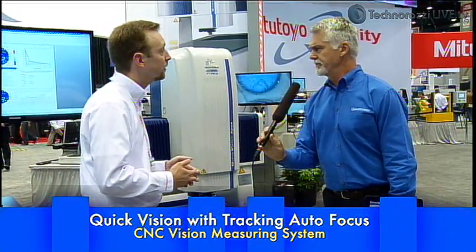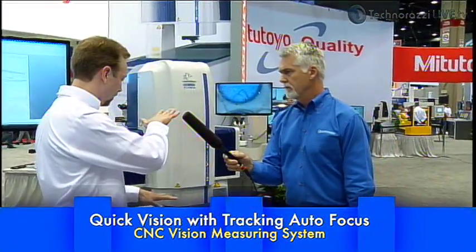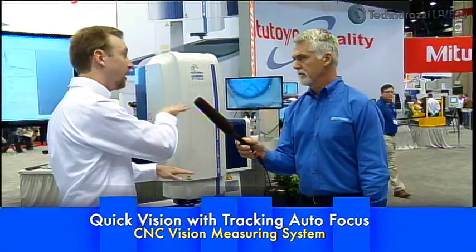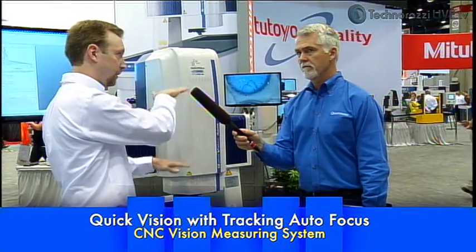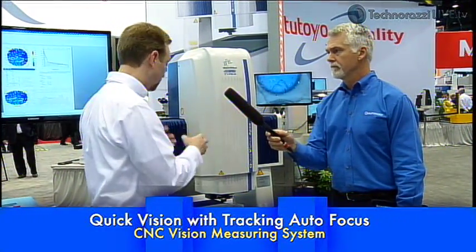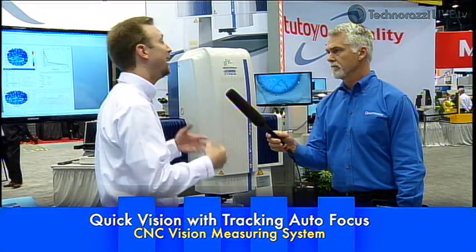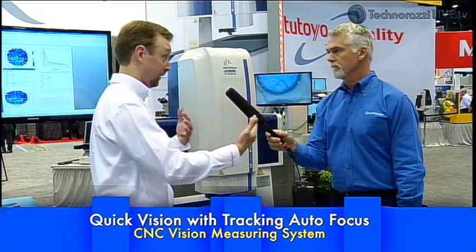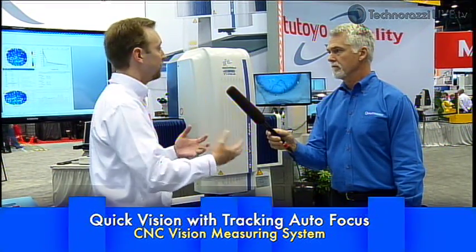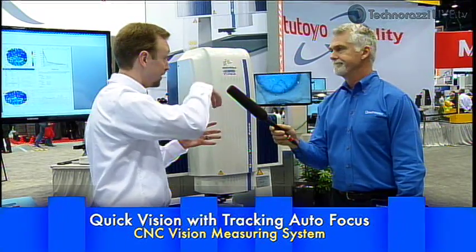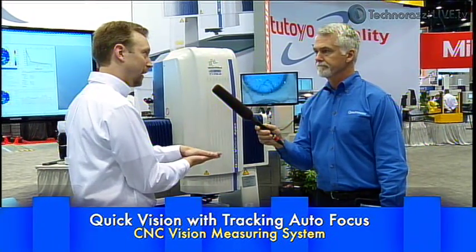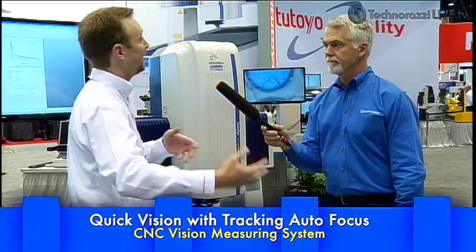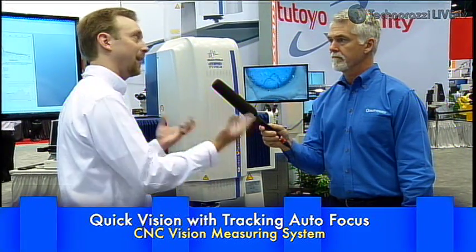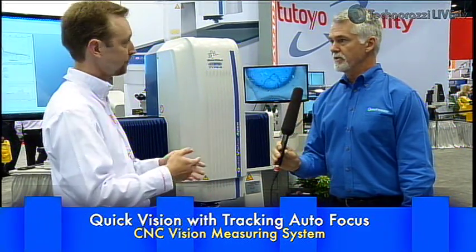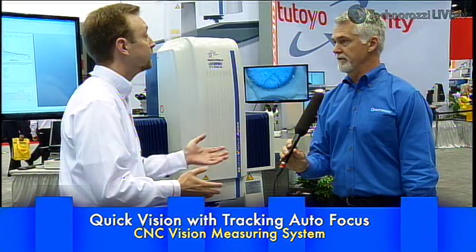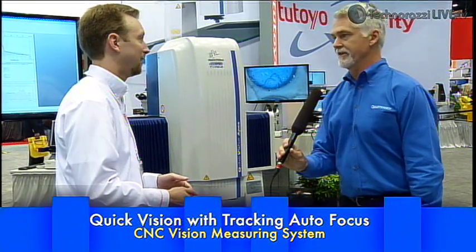And what is pattern focus? The camera normally can focus on a surface. The problem is it's looking for contrast as it focuses. So if it's a very smooth surface like glass or mirror finish, it might not be able to see the contrast that it needs to do that focus. So pattern focus projects a shadow into the light path. It can focus on that shadow so that it can succeed on a focus where it might fail otherwise, depending on the surface. Okay, so it's projecting a pattern on there that helps it, and then it's focusing. Okay, I got you.